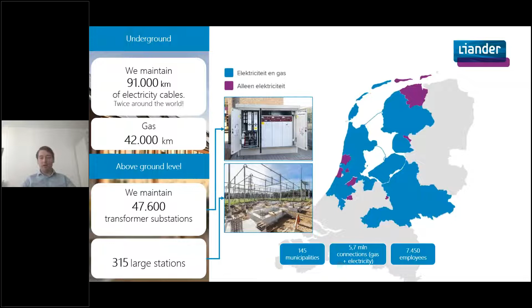In the electricity system, electricity is centrally produced mostly by gas and coal-fired power plants, and more decentralized also in neighborhoods and other areas. New solar and wind farms are deployed, but generally it's produced centrally, then transported by TenneT, the high voltage grid operator, via the extra high voltage and high voltage networks. There's a coupling with the grid of Liander at the 150 and 110 kV voltage level, where it's transformed into medium voltage, mainly 10 kV and 20 kV, distributed across towns and cities, and down to even lower voltage levels, familiar at 400 volts.